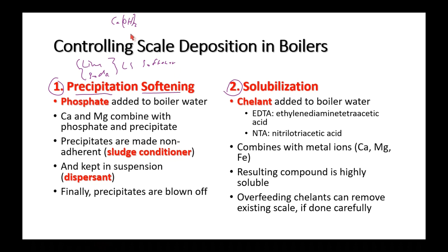Oh, that'll work. This will take care of any temporary hardness that leaks in, but we are adding hydroxide, and too much hydroxide is a bad thing. We don't want to add all this extra hydroxide into the boiler. We're going to get caustic embrittlement, under-deposit corrosion, caustic gouging, and so on. So we don't want to add calcium hydroxide. Well, what about the soda ash?